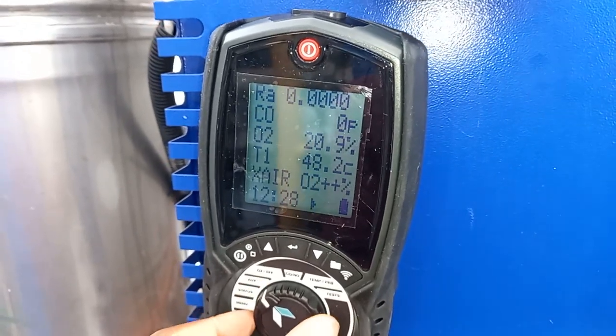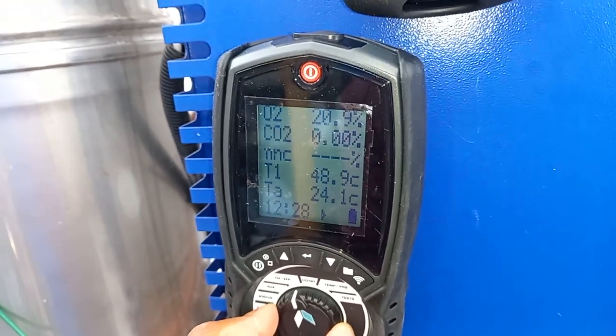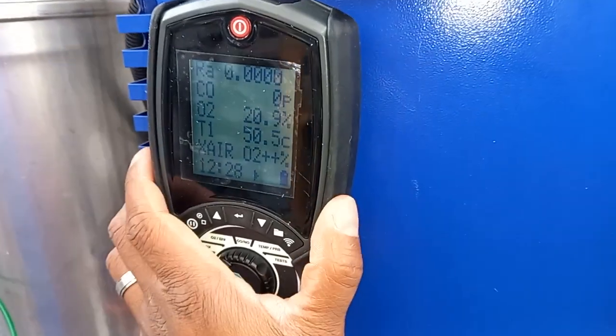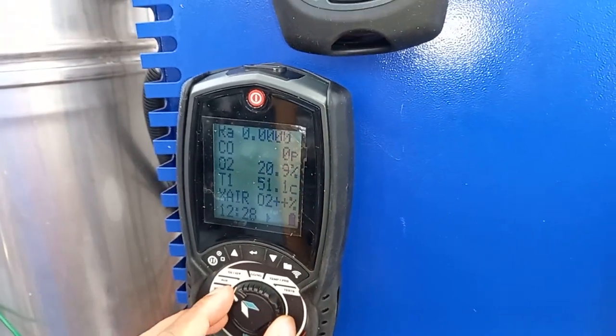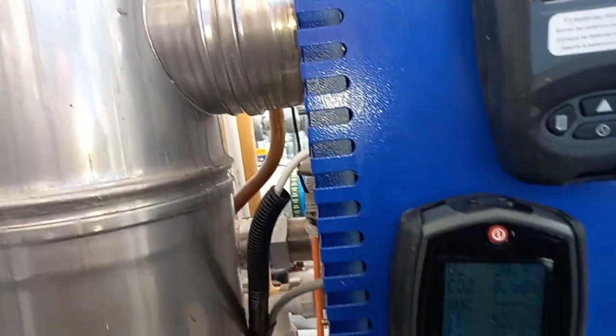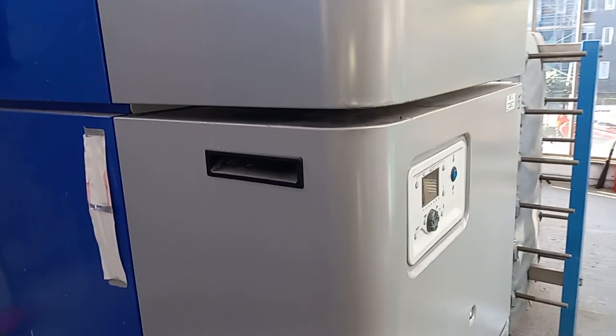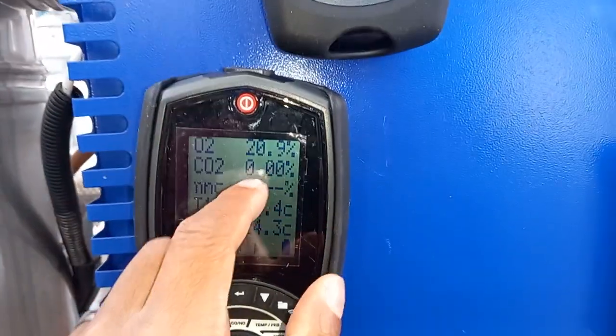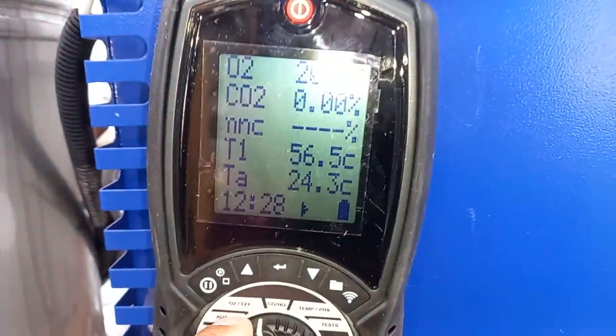And then I have to switch on here to get my different readings, so my CO2 and so on. My pump is running so I'm waiting for my CO2 readings to come on. Okay, my boiler's gone off at the moment. I'll wait for it to come back on. You can see on here it isn't showing the CO2 reading but it's showing the flue temperature. It will show it in a moment.